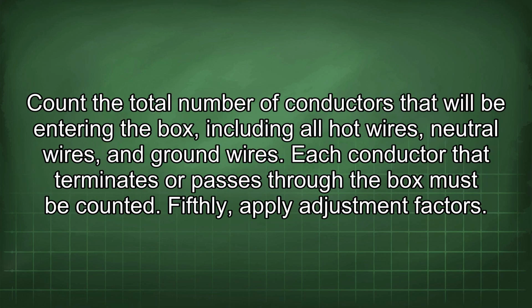Fourthly, count the number of conductors. Count the total number of conductors that will be entering the box, including all hot wires, neutral wires, and ground wires. Each conductor that terminates or passes through the box must be counted.